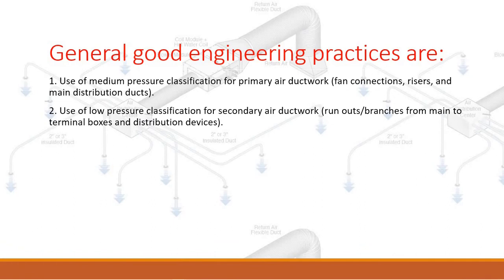General good engineering practices are: one, use of medium pressure classification for primary air ductwork, fan connections, risers, and main distribution ducts; two, use of low pressure classification for secondary air ductwork, run-outs and branches from main to terminal boxes and distribution devices.